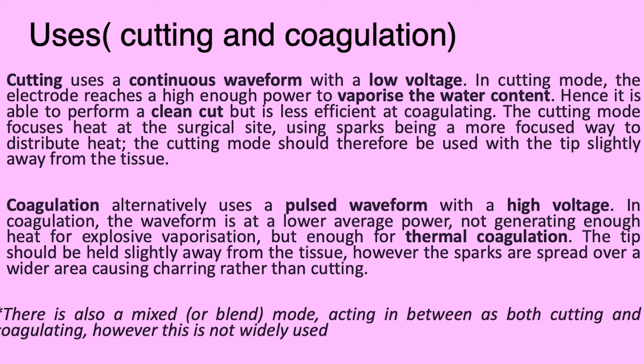Surgical diathermy is used for cutting and coagulation. Cutting uses a continuous waveform with low voltage. In cutting mode, the electrode reaches a high enough power to vaporize the water content, allowing a clean cut, but is less efficient at coagulating. The cutting mode focuses heat at the surgical site using sparks — a more focused way to distribute heat. The tip should be held slightly away from the tissue.